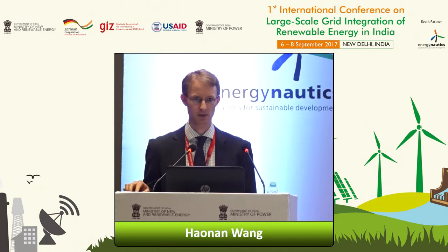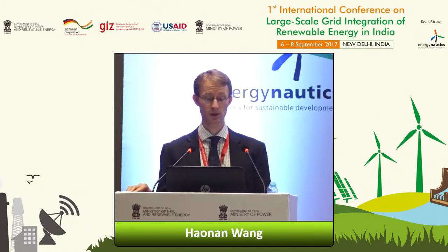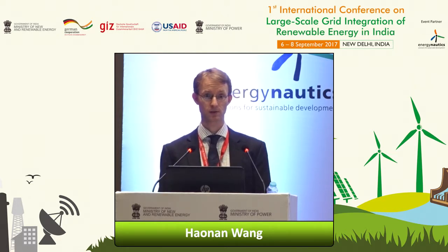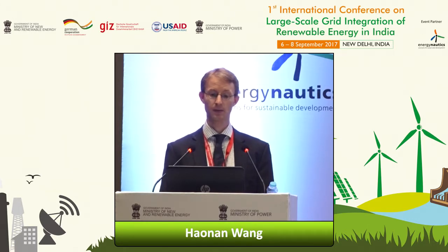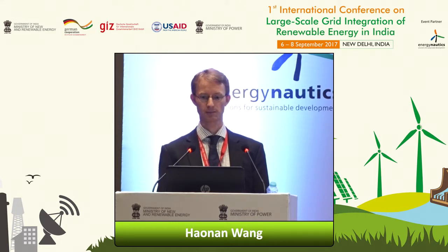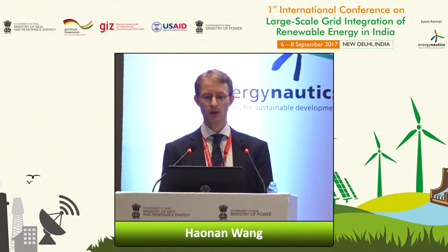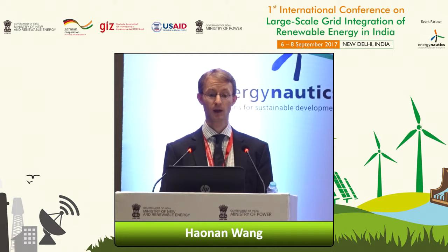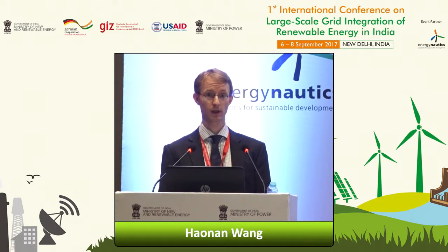So why are we doing that? The major driver in the German context is that conventional bulk power plants are substituted by distributed generation. So this system is turned upside down. That means we need reactive power sources, which are less and less provided by conventional large-scale bulk power plants in transmission. Then we see more cabling in the system due to the increase of reliability, which I showed at the beginning. Cables have reactive power requirements, and so there is an additional need for inductive reactive power.